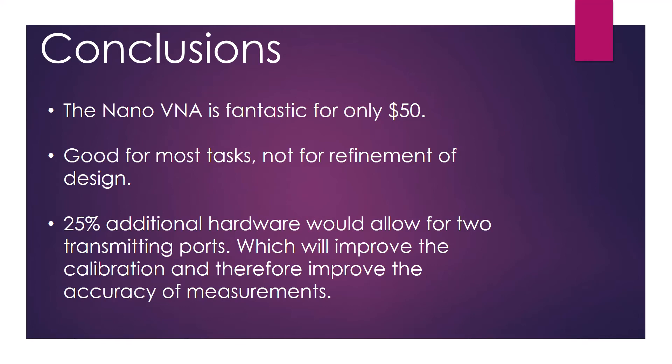A serious downside to the Nano is that only one of its two ports can be used for transmitting a signal, whereas most standard VNAs allow for two transmitting ports. For a little extra cost, the Nano hardware could be improved to add a switch to allow for two transmitting ports. This would improve calibration, therefore accuracy, which would make the Nano a serious competitor.